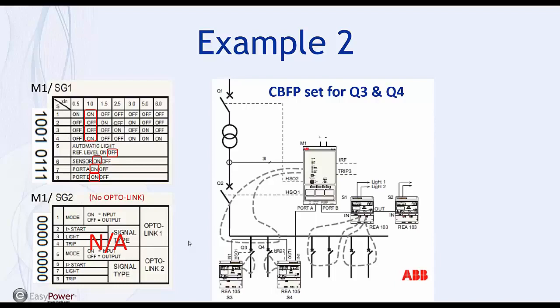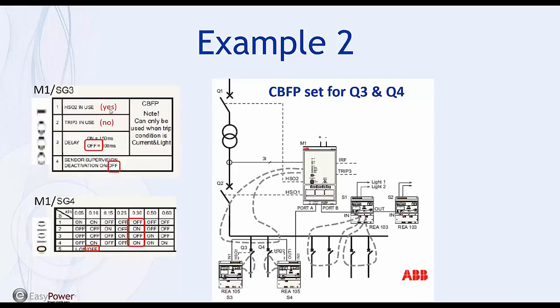We look at setting group 3, that's our breaker failure. On the main, we will have breaker failure for Q2, set at 100 milliseconds and supervise the loop. In this case, we're not using the ground, so we'll turn that off, and so these settings don't apply.